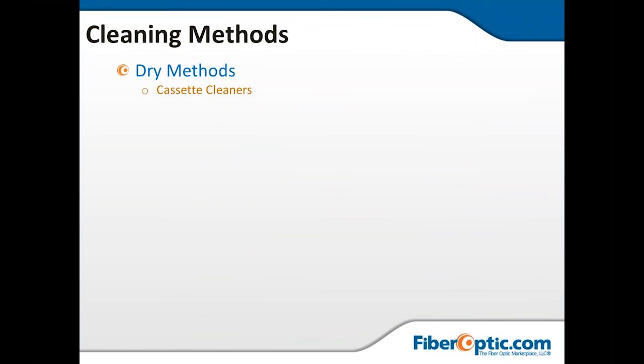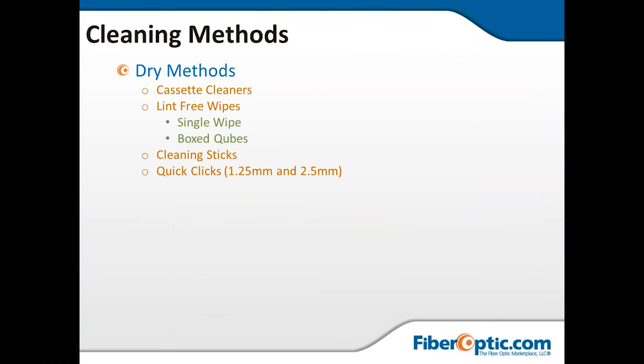Now, these are the different types of dry methods. You've got your cassette cleaners, your lint-free wipes, and you've seen the single wipes, and also the box cubes that are out there. Cleaning sticks, both 1.25 and 2.5 millimeter. And you've got your quick clicks. A lot of people call them one clicks. One thing you've got to remember about those: a single click is a single cleaning operation. It doesn't mean that it's one click and you're clean. So that's important to know.